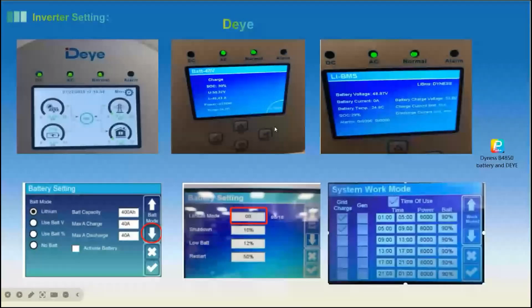Okay, so we make a conclusion here. On the inverter, actually, we need to set 3 parts. The first part is to select the battery mode, select the lithium battery, and then confirm the battery setting. It should be 0000, which means Dyness battery. And after the battery is selected, we come back to the home page, click the battery icon, and it will go to this page. There will be the BMS communication, and we can check the discharge current limit on this page.